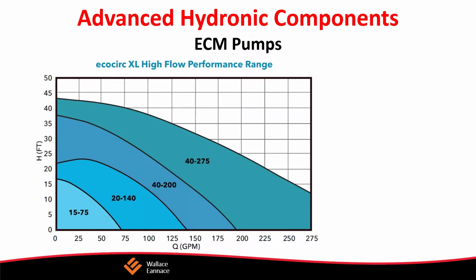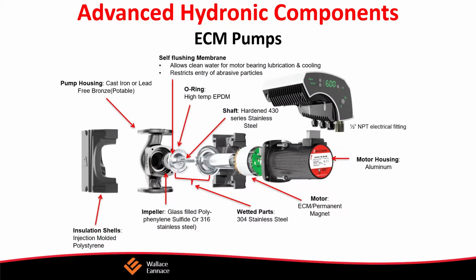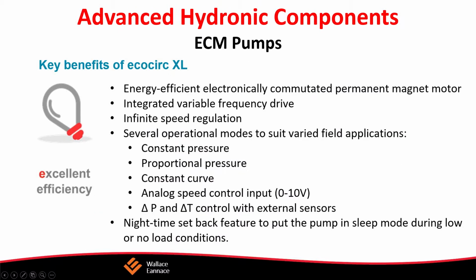And so I'll talk about later, there are big advantages to that. There's also, you can set it for temperature. And it has a thing called eAdapt, where it'll auto learn what your system is needing, and it'll also go into night mode, and it'll look for its optimal point based on what the demands are made on the pump. And once again, it also has a digital display, which can show you both the feet of head, the GPM, and the power usage in watts. It'll show you feet of head, it'll show you GPM, it'll show you watts.